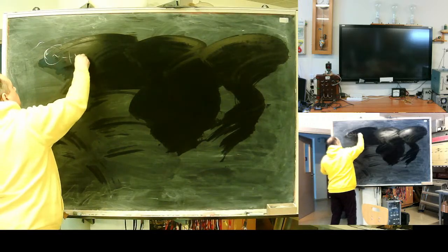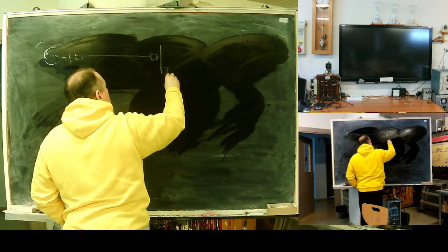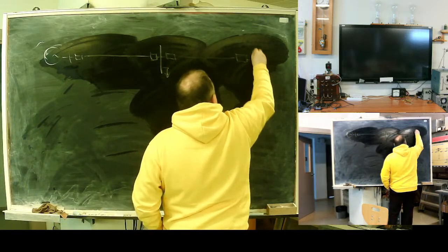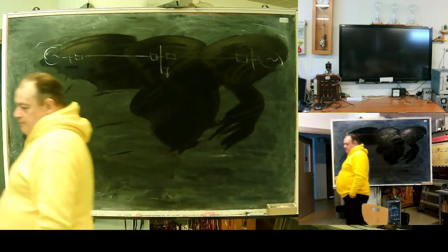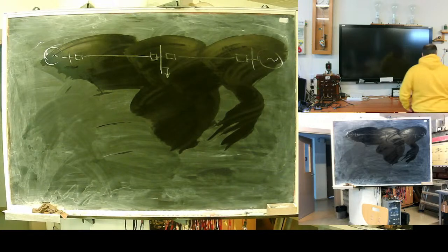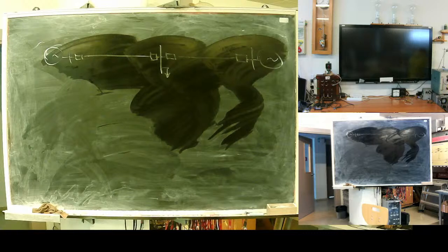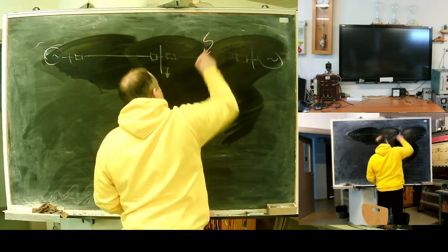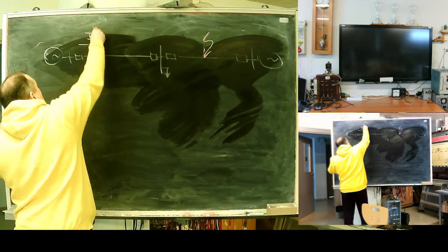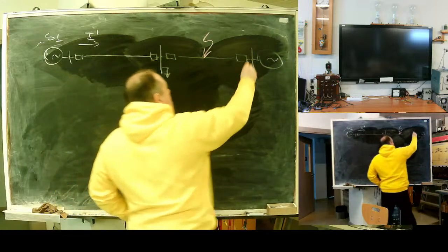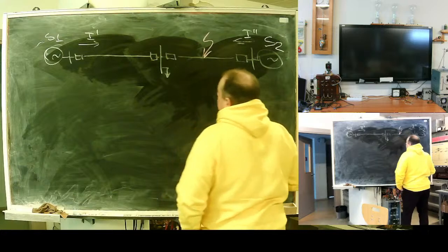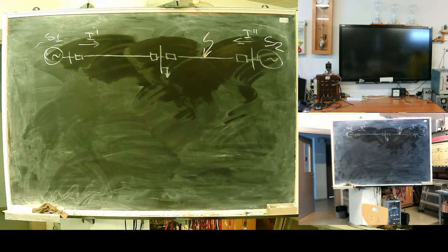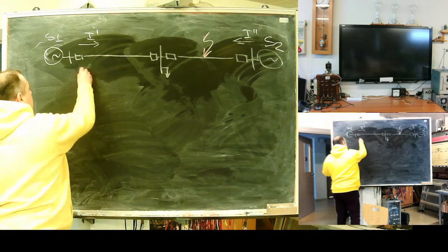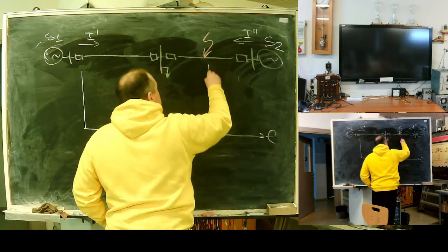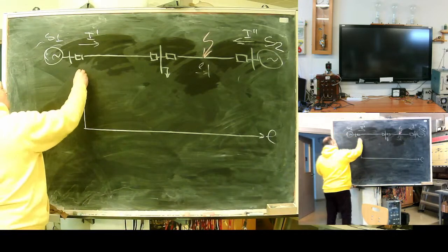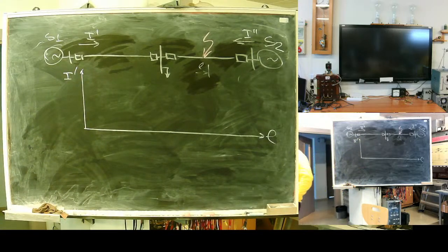You have, say, source 1, load in the middle, and source 2. All such kind of scenarios can be reduced to a double side fed line. Fault, current from the side of, let's say, system 1 and current from system 2. Is it clear? Yeah, it's very simple. Now, can I draw a very simple chart? Distance to the fault, current I1. And it depends on distance to the fault.